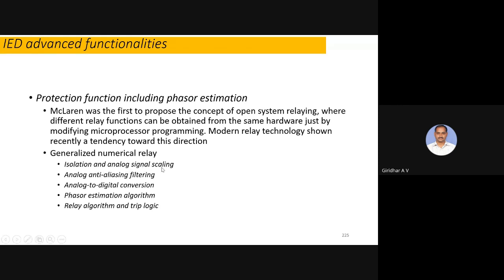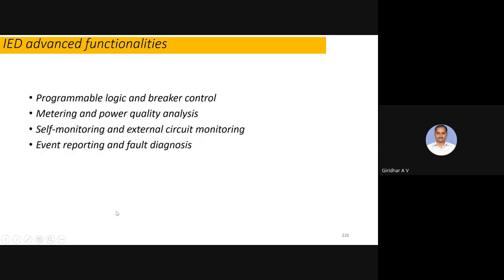Isolation and analog signal scaling will be there. Anti-aliasing filters will be there. There is estimation, relay algorithm, and trip logic we can do. In that way, a multifunction relay can happen. Even programmable logic and breaker controls without PLCs, it will have its own control. So externally you do not need programmable logic controllers. This IED itself will handle the logic inputs and outputs of the protection functions.